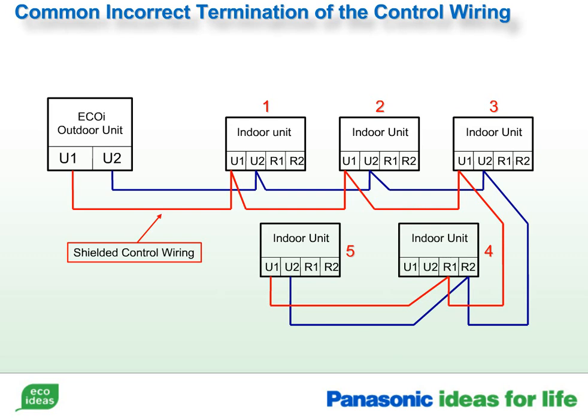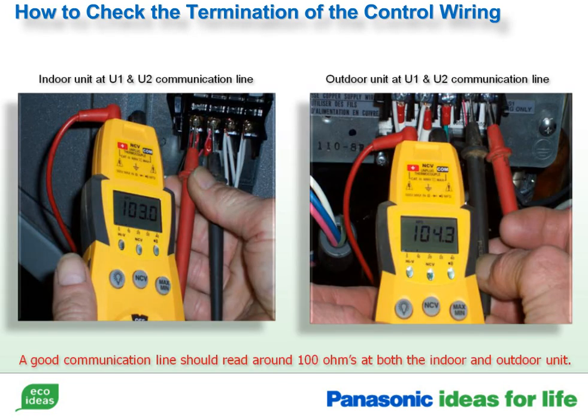wired in series. Another common mistake is using standard T-stat wire, instead of using shielded wire. This can cause noise, intermittent, or complete loss of communication. A good way to check for a break in the control wiring is to check the ohm reading anywhere on the S-net. Between U1 and U2, you should read about 100 ohms.